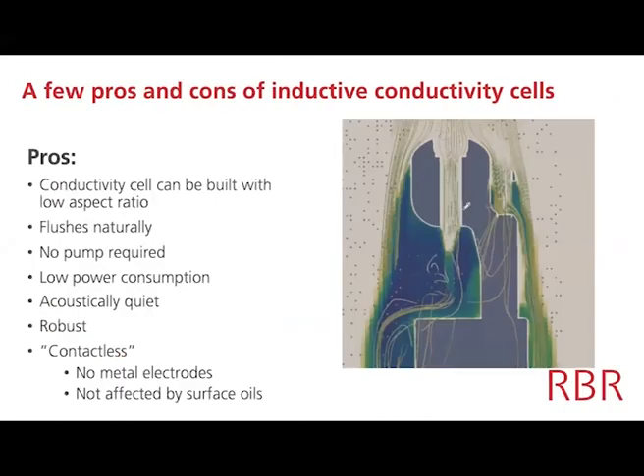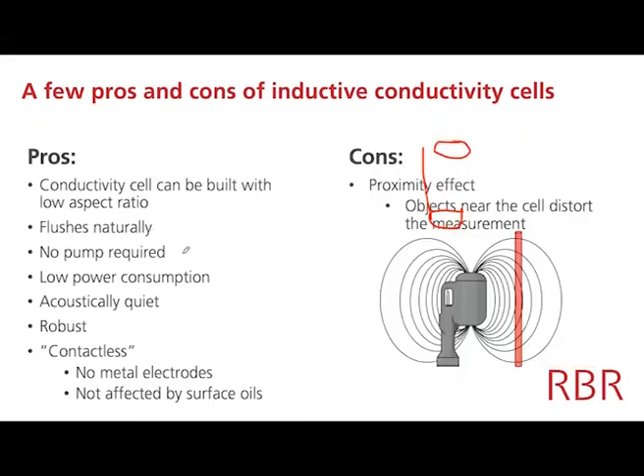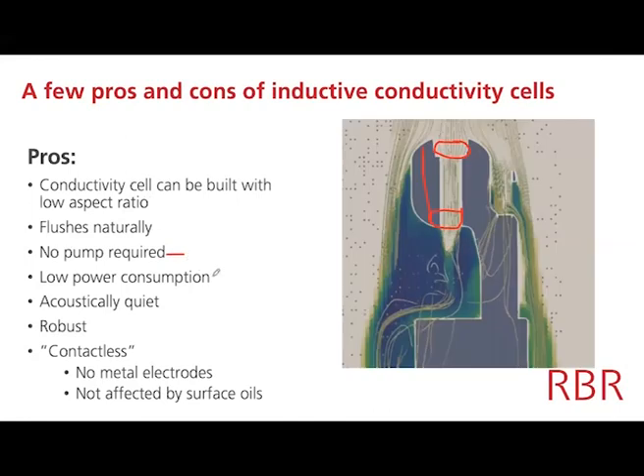Now, a couple of pros and cons about this technology. One is that these cells can be built with a low aspect ratio, which means the cylinder can be relatively squat. In other words, the bore through the center of the cell can be large compared to the length. What this means is that the cell can flush naturally just by the motion of the instrument through the water. That means we don't need to pump it, so without a pump the power consumption is quite low. It also means the cell is acoustically quiet, which is important in particular on glider applications with passive acoustics or turbulence measurements. There's no pump creating any noise or vibrations.